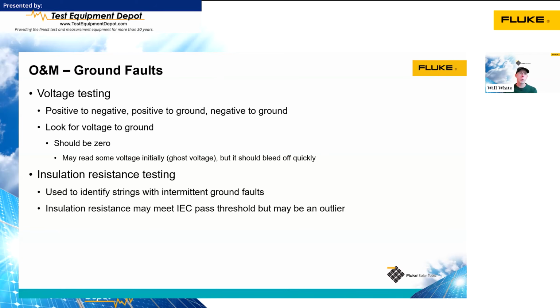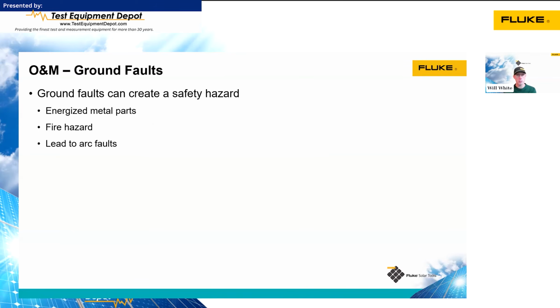testing at. So when I went out into the array, I found the string, and I found an MC4 connector between modules laying on the roof in a puddle. So that's why the insulation resistance test was less. Once I pulled it out of the puddle, hung it up properly, let it dry for a little bit, it passed the test with 2 giga ohms, like everything else in the system.